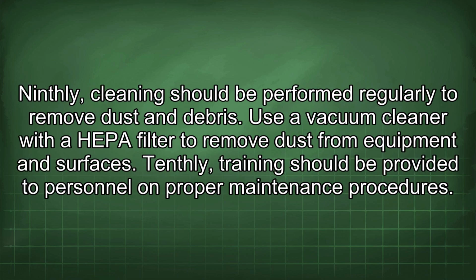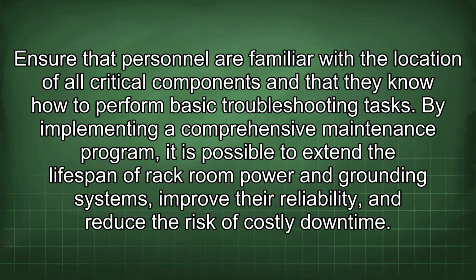Ninthly, cleaning should be performed regularly to remove dust and debris. Use a vacuum cleaner with a HEPA filter to remove dust from equipment and surfaces. Tenthly, training should be provided to personnel on proper maintenance procedures. Ensure that personnel are familiar with the location of all critical components and that they know how to perform basic troubleshooting tasks. By implementing a comprehensive maintenance program, it is possible to extend the lifespan of rack room power and grounding systems, improve their reliability, and reduce the risk of costly downtime.